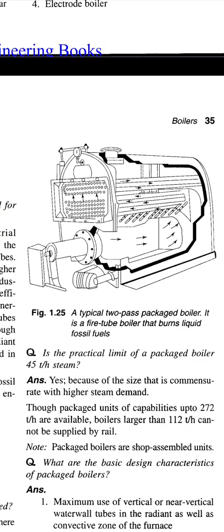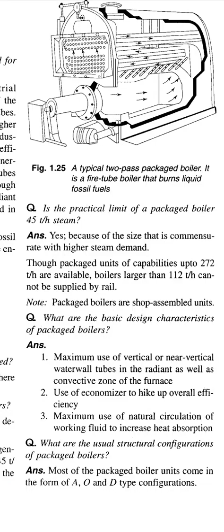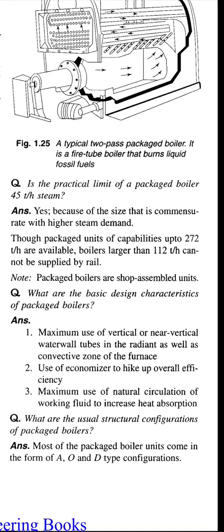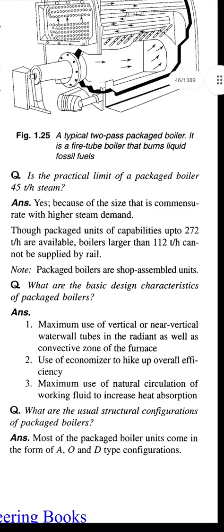The next question: is the practical limit of packaged boiler 45 tons per hour steam? Yes, because of the size that is commensurate with higher steam demand. Through packages, units of capacities up to 272 tons per hour are available. Boilers larger than 112 tons per hour cannot be supplied by rail. Note: packaged boilers are shop assembled units.